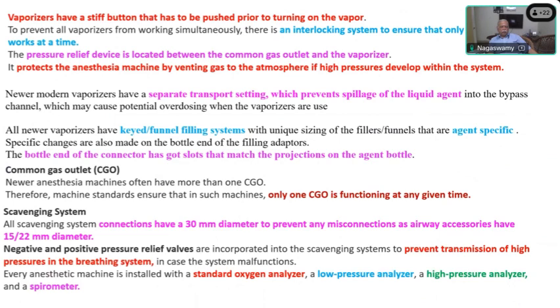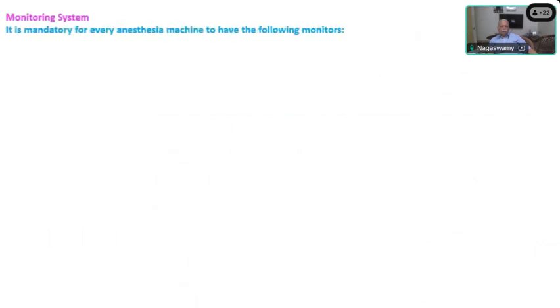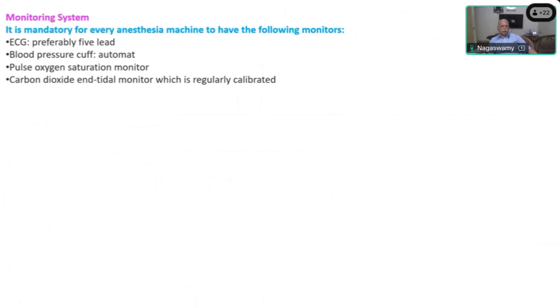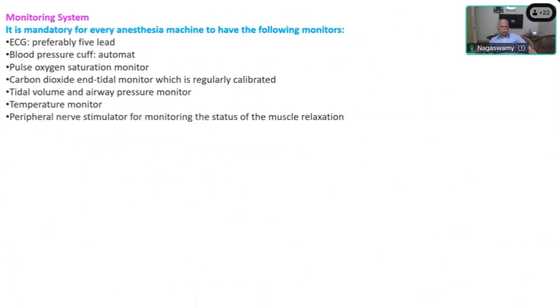And every anesthesia machine is installed with a standard oxygen analyzer, a low pressure analyzer. These are all present in the modern workstations. These are not present in the older machines. That's why I told you, if the question is worded as anesthesia workstation, you have to include all these answers: a low pressure analyzer, a high pressure analyzer, and even a spirometer. And coming to the monitoring system which comes along with modern anesthesia machines, these have become the mandatory monitors. One is ECG with a 5-lead configuration, blood pressure for automatic NIBP measurement, pulse oximetry, end-tidal CO2 monitor, tidal volume and airway pressure monitor, and temperature monitor. Sometimes a peripheral nerve stimulator is also included, especially for patients undergoing neuro procedures or other super specialty theaters.